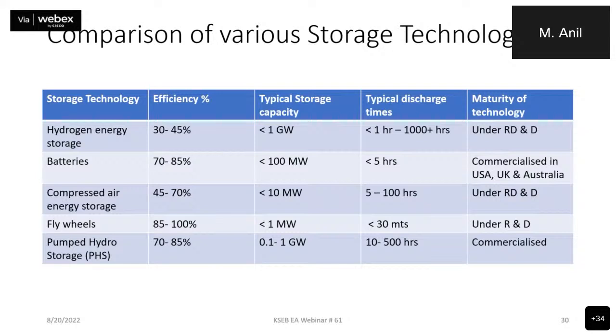Typical discharge times for hydrogen energy, less than 1 hour to 1000 plus hours. For batteries, it's less than 5 hours. Compressed air energy storage, 5 to 100 hours. Flywheels, less than 30 minutes. And pumped hydro storage, 10 to 500 hours.